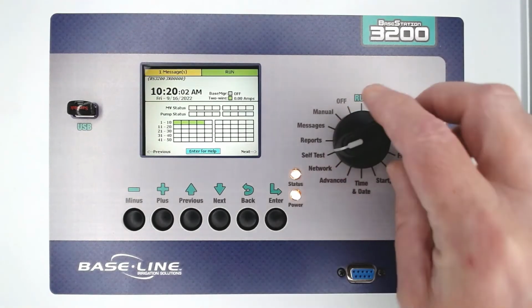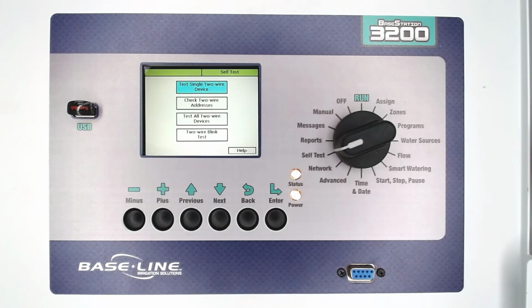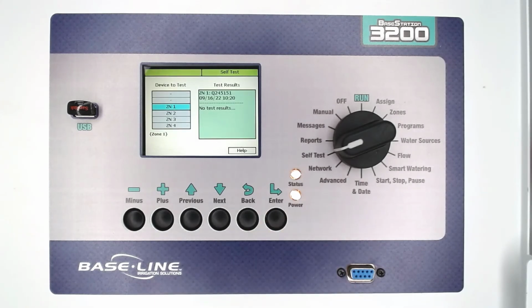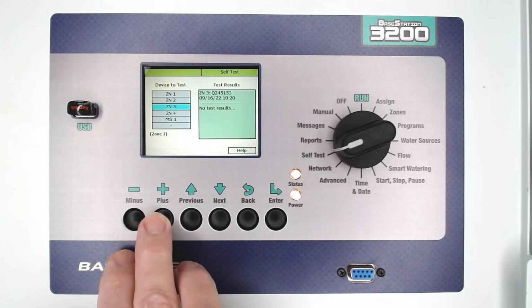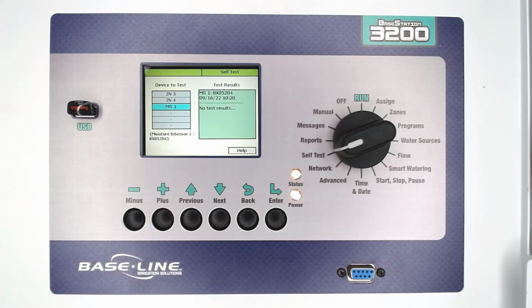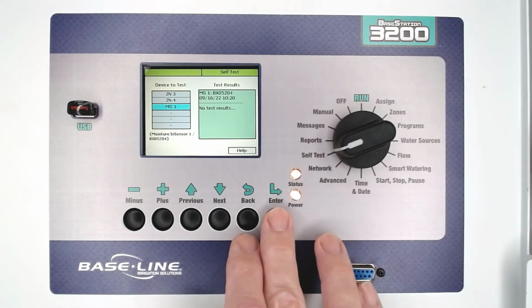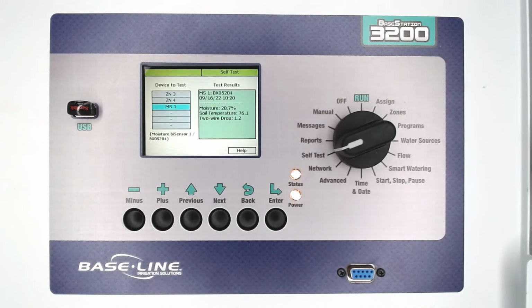At the controller, turn the dial to the self-test position, highlight the menu Test Single 2-Wire Device, and press Enter to open that menu. Here I can test any device that's been assigned during the search and assign process. Scroll through the list until you find the device you want to test. In this case, it's Moisture Sensor 1. With MS1 highlighted, press Enter to start the test.